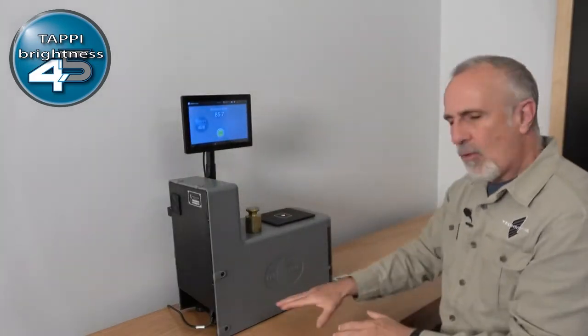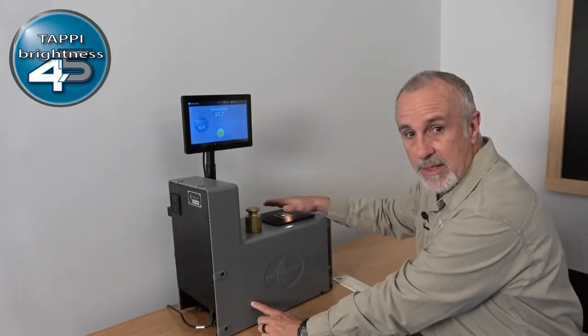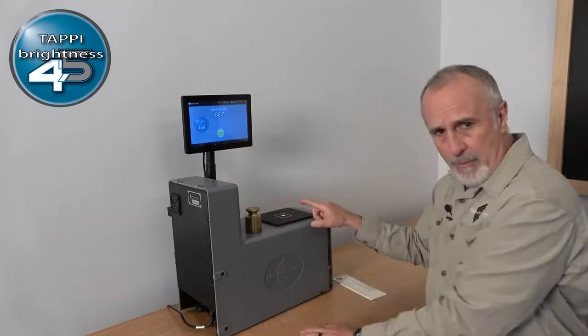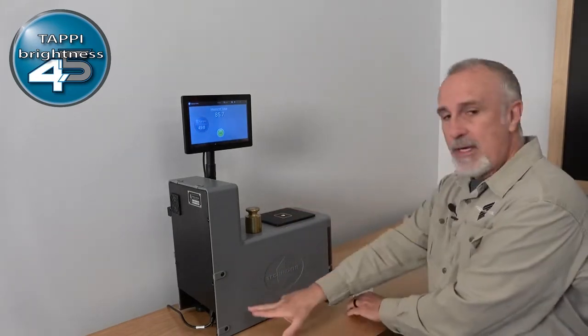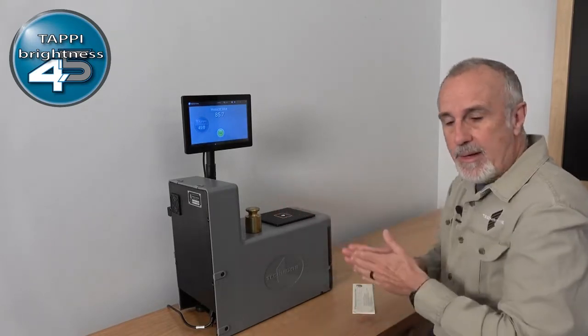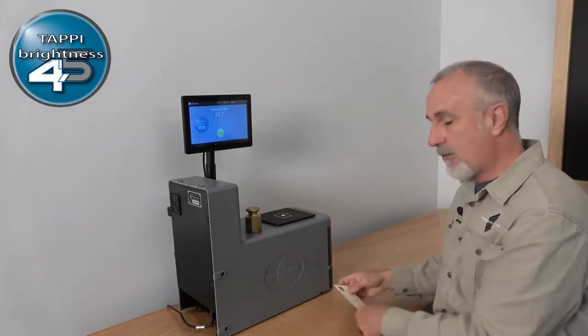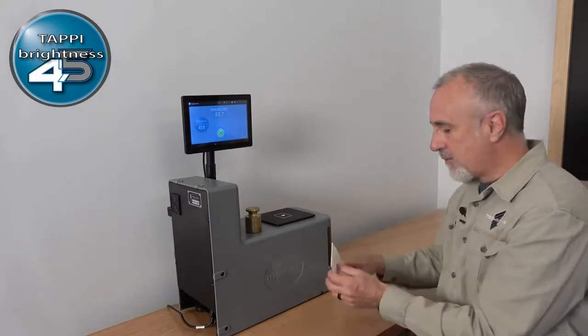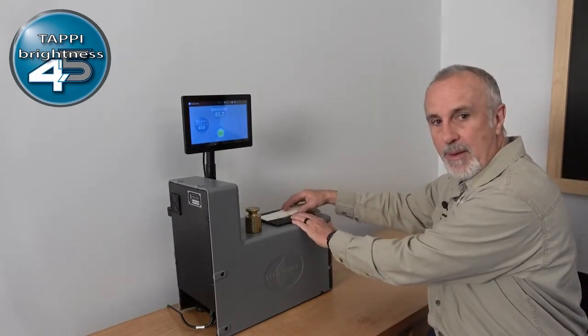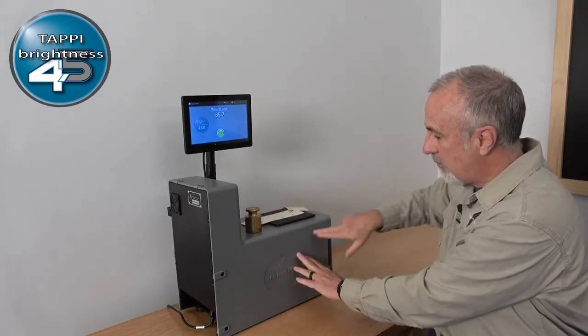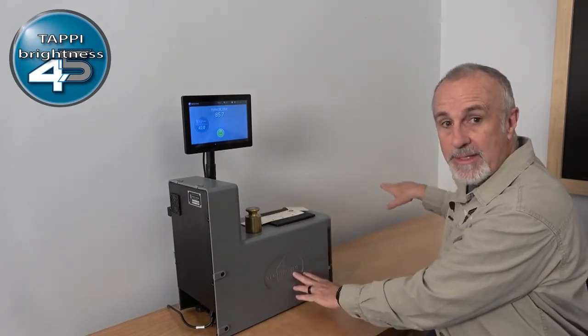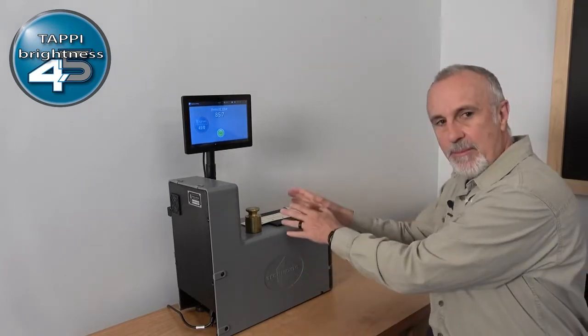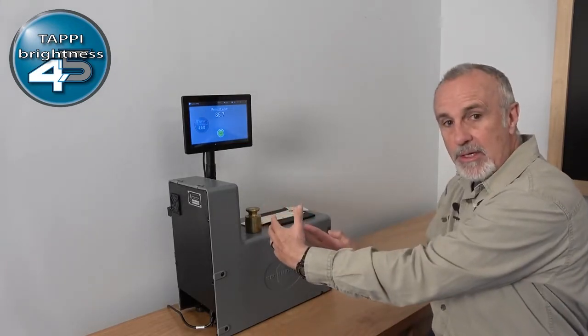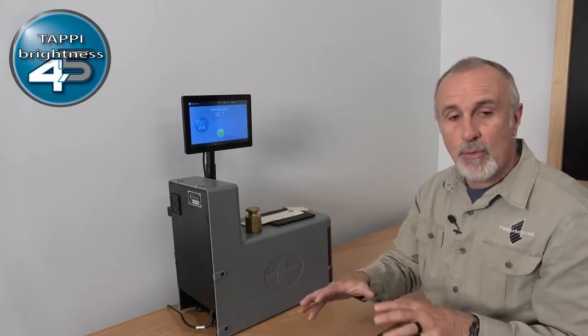Here, the orientation of the instrument has stayed the same, so the lamp still sits here and it's still illuminating this sample port here. But you have to keep in mind that the orientation now is this way, not this way, as far as the operators and testing go. So just like the previous method, I would continue to load my samples in this way because the machine direction is still going on this axis. Whether you have it set up this way or rotated 90 degrees, you always have to be mindful of the orientation so I measure my sample correctly.